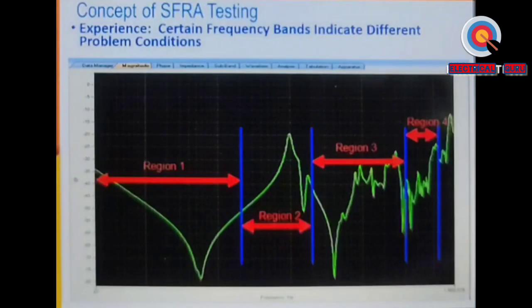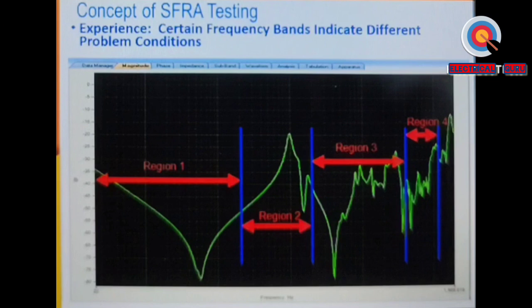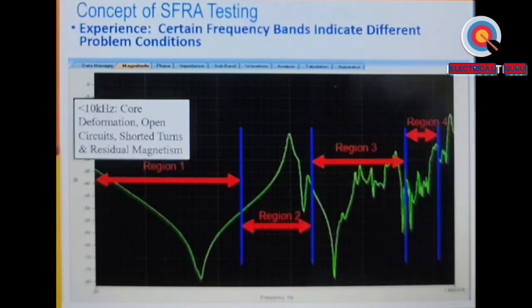So now how do we determine the fault inside the transformers? So we have identified that the response can be divided into 4 different regions. The test is conducted from 20 Hz to 2 megahertz. This is a logarithmic scale. Zone 1 or region 1, we say it is less than 10 kilohertz. So when I am supplying a signal below 10 kilohertz, whatever distortion I see in this region shows that there is a deformation, open circuits, shorted turns, and residual magnetism. So if your core has residual magnetism, it may also show you a distortion in this region.